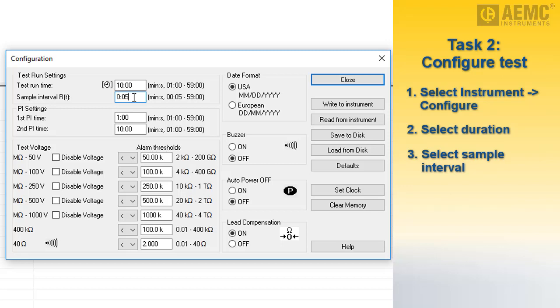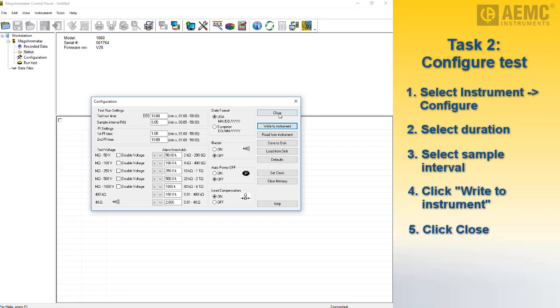The Configuration dialog box includes a number of other fields for selecting features, such as the calculation to determine polarization index, alarm thresholds, lead compensation, and other features. These are all described in detail in the help system that comes with the DataView Megohmmeter control panel. For the sake of simplicity, we will leave these at their default settings and click Write to Instrument to update the instrument configuration. Then click Close.